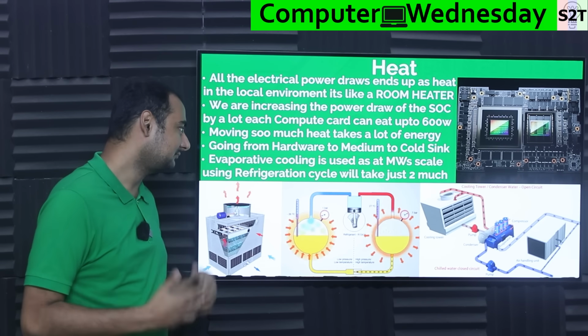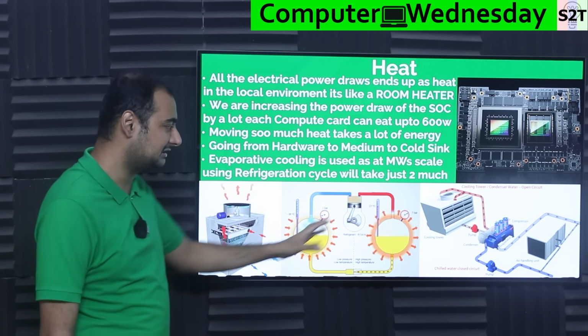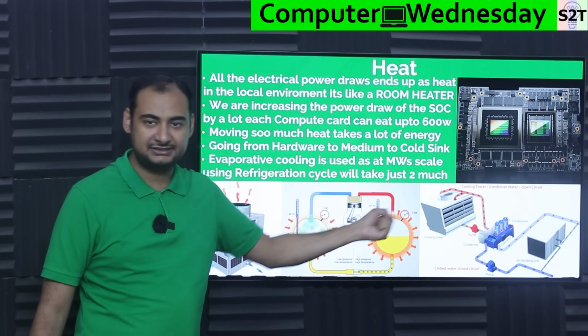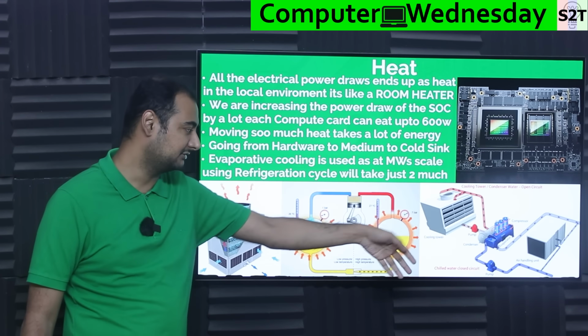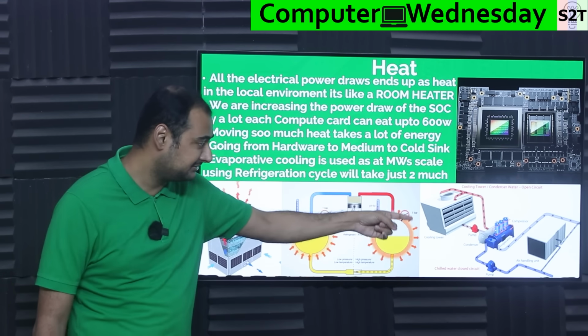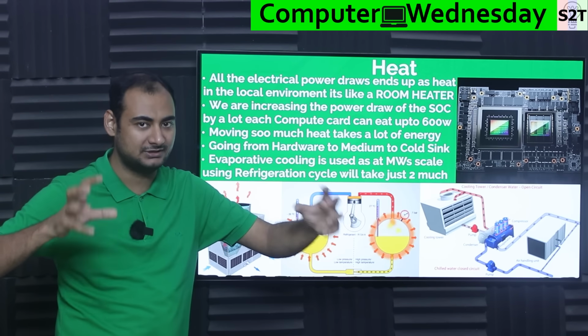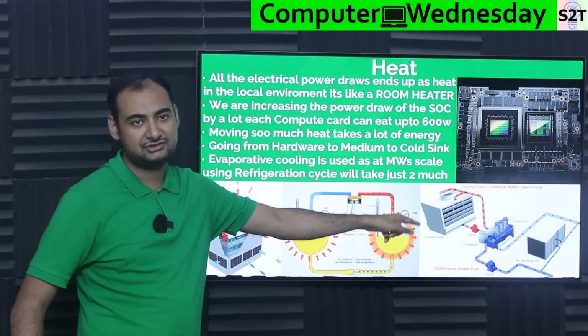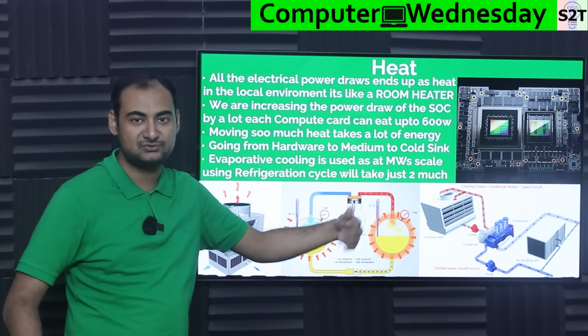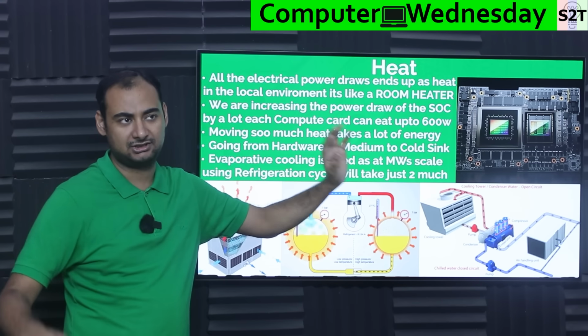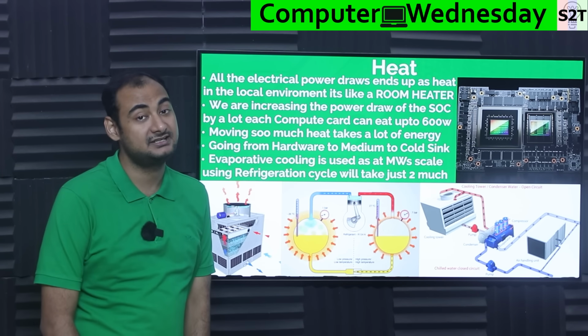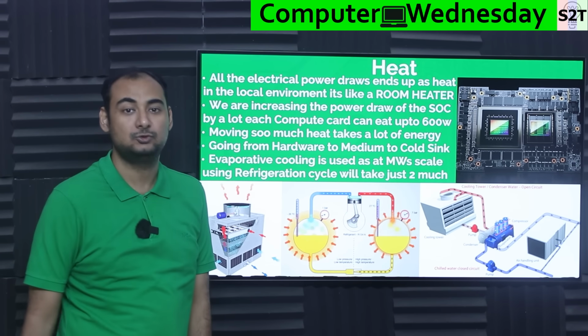So what we do is have the normal refrigeration cycle that takes heat from one side, as in your servers, and dumps it into another medium. That other medium generally is a shell and tube heat exchanger. The shell and tube heat exchanger generally has a cooling medium, and that cooling medium is water. Water goes into a radiator. Now you might ask, why is water being lost? That radiator is open - it's basically a swamp cooler.